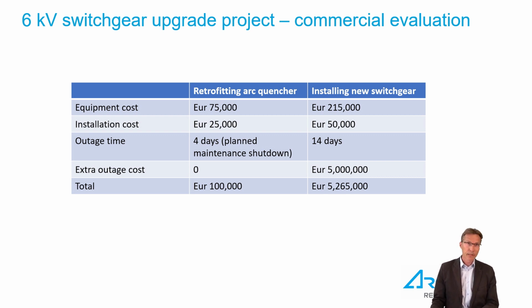So this comes to the next row on extra outage cost. We can say in the retrofitting activity, the extra outage cost is 0, since it's done during the maintenance shutdown. If we calculate 10 days extra outage time for installing a new switchgear, with these round figures that we are using, you get to the value of 5 million euro cost for the outage time on installing the new switchgear.